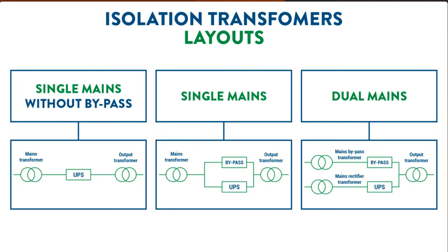They can come as single mains with a bypass system. So the isolation transformer is isolating the whole UPS system with its bypass from the grid, and there is an output transformer that isolates the whole UPS system from the loads, or dual mains where there is the UPS and the bypass line that are supplied from different mains lines, which can be due to usage of separate circuit breakers on the same panel, or to have separate generating lines, one coming, for example, for the UPS from the grid and the bypass line being supplied from a generator.